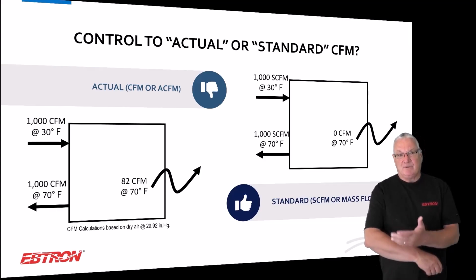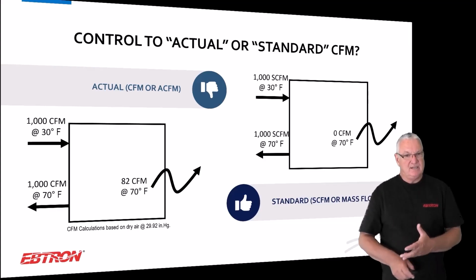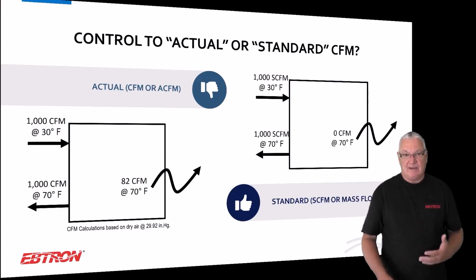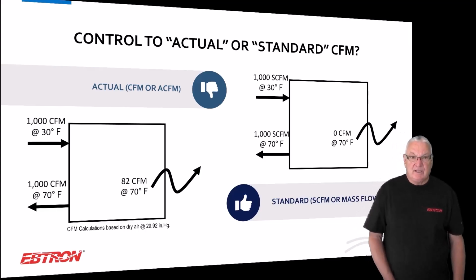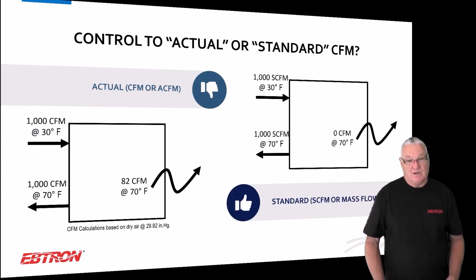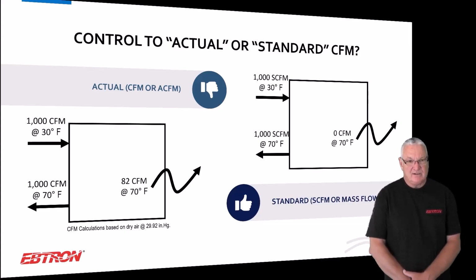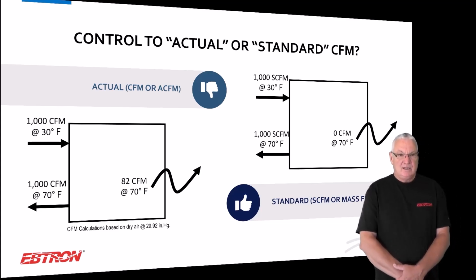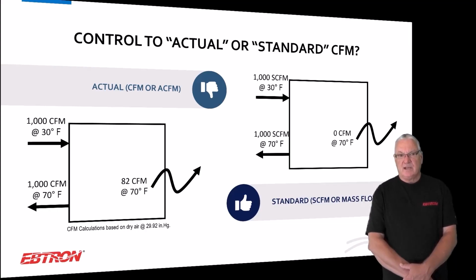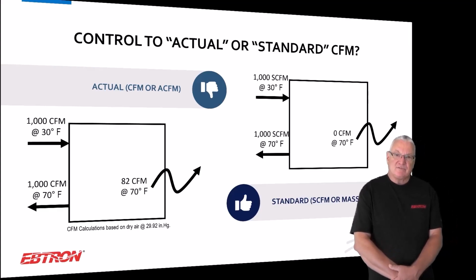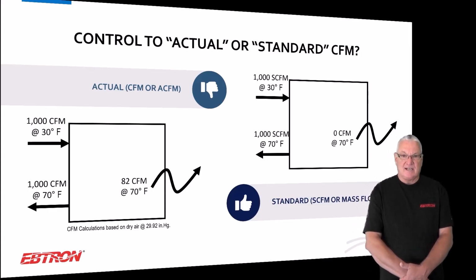But anyhow, here, if you look at the left, that's actual, or what we typically deal with when we go out and measure. Even the way the EBTRON comes out of the factory is actual, because that's what you all want, okay? But I don't know if you realize this, 1,000 CFM, actual CFM at 30 degrees of air coming in, and 1,000 CFM, actual CFM of air at 70 degrees going out, does not result in a net neutral building. It results in a positive building. And it's an 82 CFM positive building. It's 8%. That's a lot. And when you look at standard CFM, which is the mass flow equivalent, 1,000 at 30 and 1,000 at 70, you get net zero.